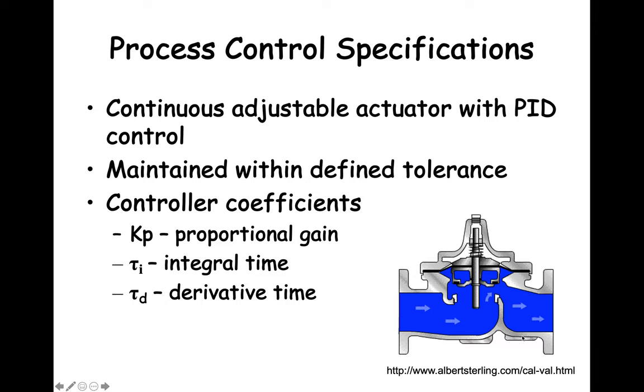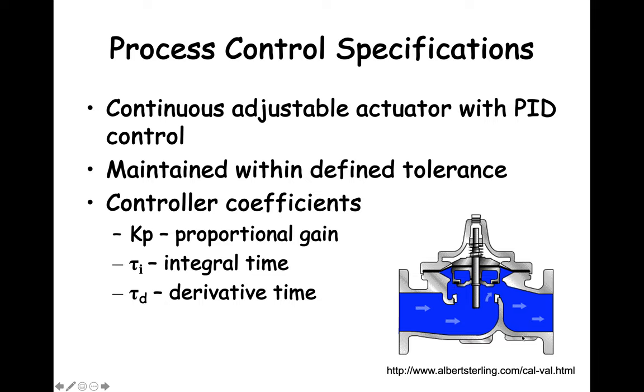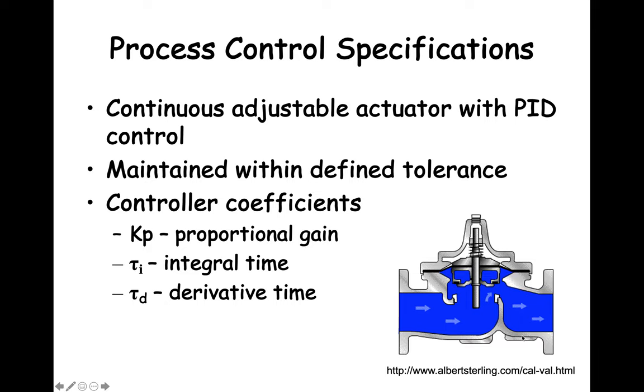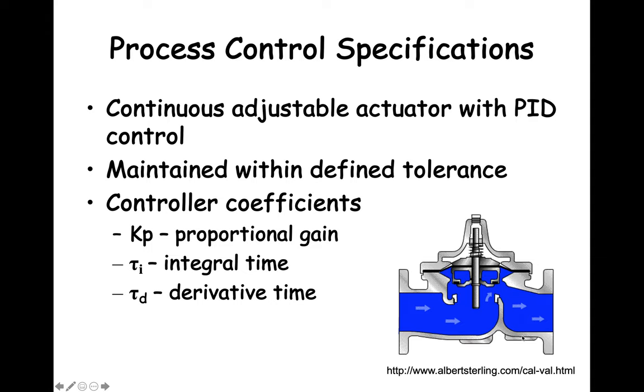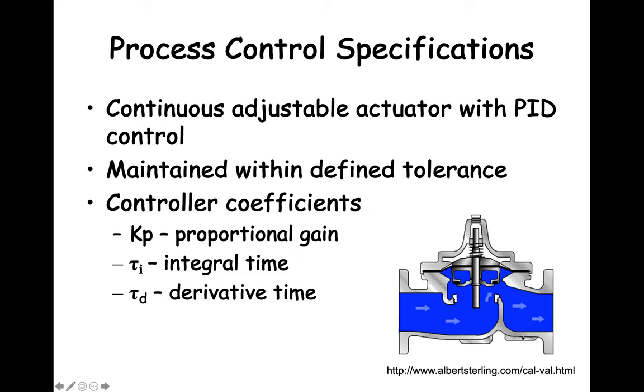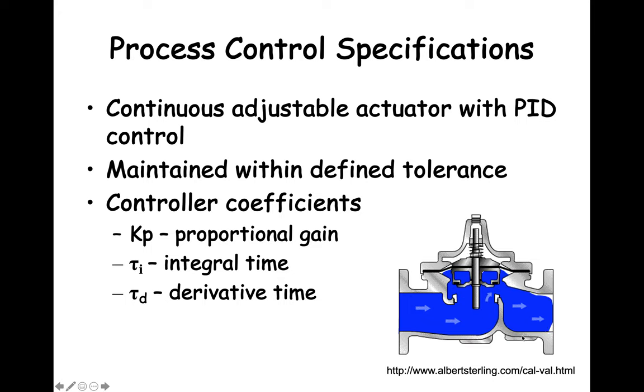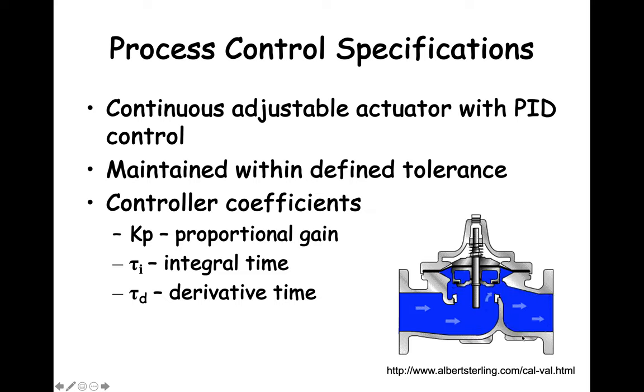One aspect of good control is staying within the user-defined tolerance limits. For example, a person using the fluid heater we have been studying could specify that he or she wants the fluid temperature to be 41.5 degrees C plus or minus 0.3 degrees C. With this type of process performance specification, the outlet temperature can be monitored to see what percentage of the time the outlet temperature is within the specified tolerance and what hopefully small amount of time the outlet temperature is outside the specified tolerance limits.